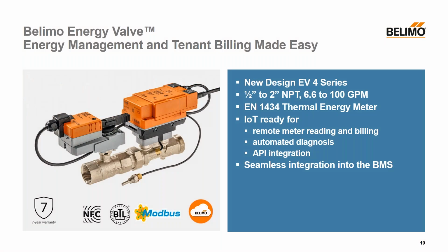So starting us off is the new 4th generation energy valve known as the EV4 series. These encompass 1/2 inch to 2 inch NPT sizes. These are found in the PGPL under the Energy Valve Pressure Independent Valves tab in section 6. What's unique about these is these innovative new EVs combine both temperature control with energy metering into a single unit. So this is the first time we're featuring an integrated thermal energy meter. These are designed to EN 1434 standards, ensuring high accuracy and reliability.